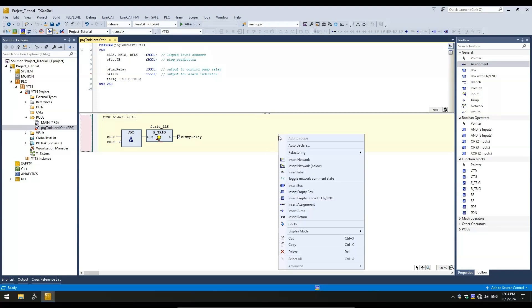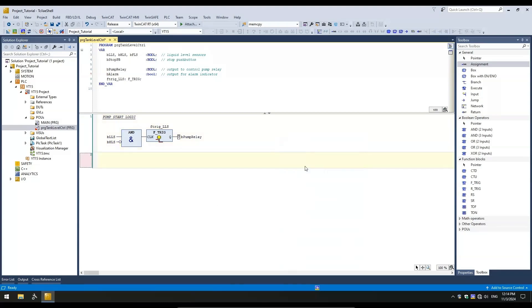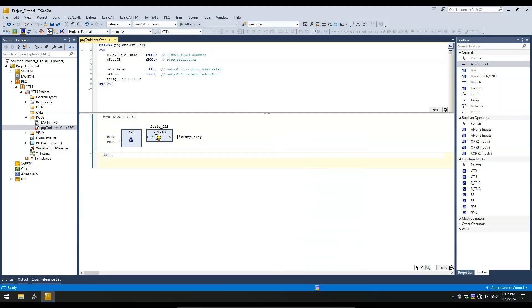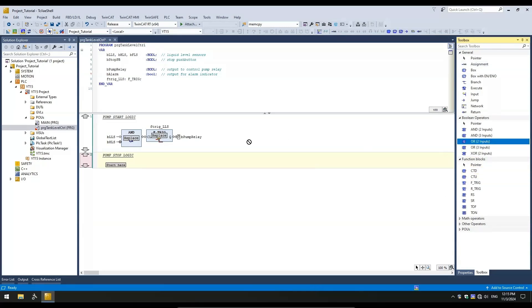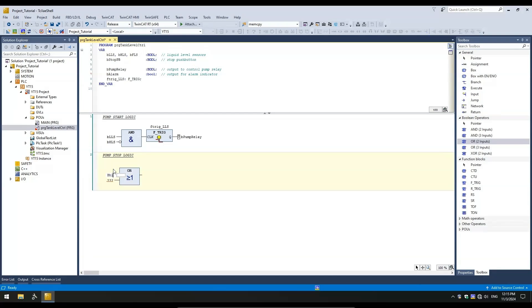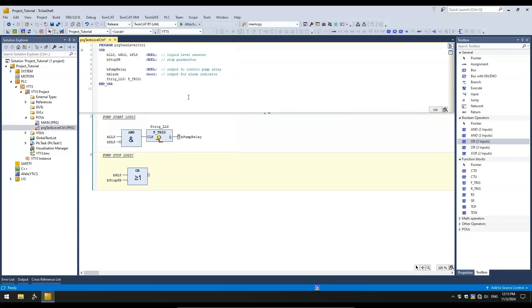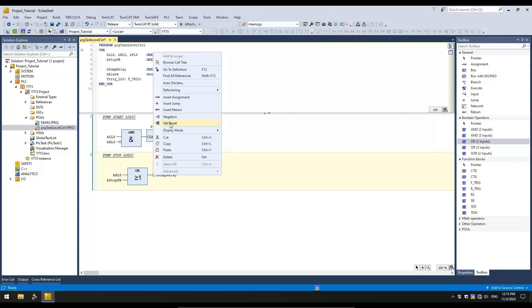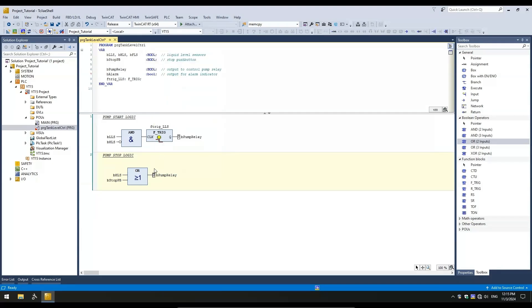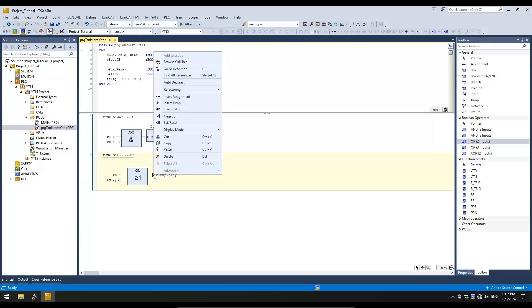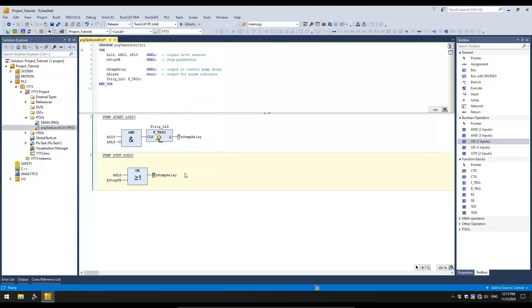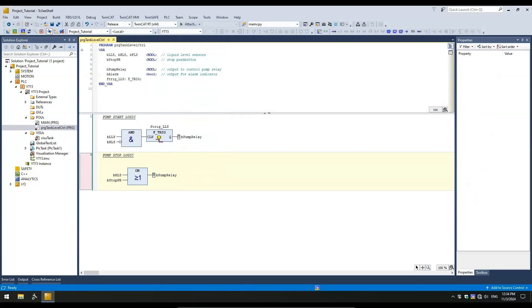Next, let's move on to the pump stop logic. Start by inserting another network below this. Enter a name for this network for clarity. Good documentation is always a good idea when programming PLCs. Once the pump starts, the filling will begin and the low-level sensor will turn back on. As soon as the high-level sensor comes on, or if the stop push button is pressed, we stop the pump. So, for this implementation, we need the boolean OR operator to reset the pump control variable. Right-click on the output pin of the block and use the insert assignment option and enter the variable name. Similar to the set instruction which latches a variable, we have the reset instruction which unlatches the variable when the conditions are true. This is indicated by the letter R next to the variable name.